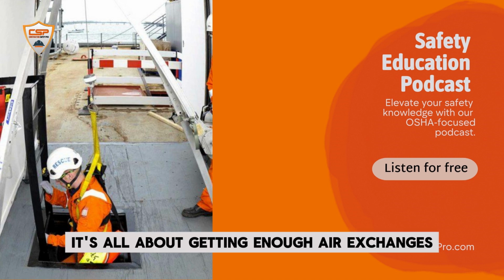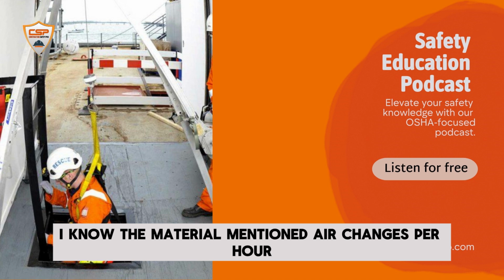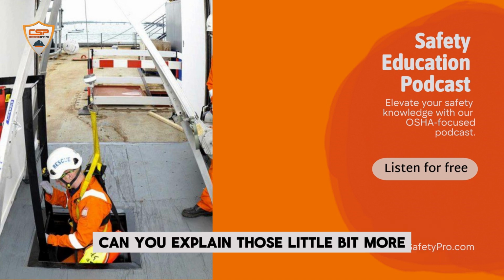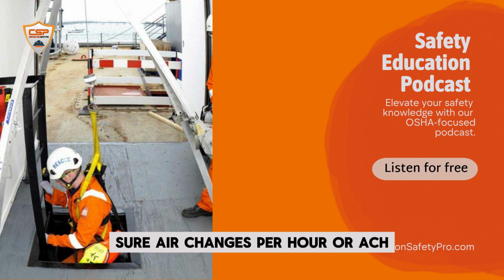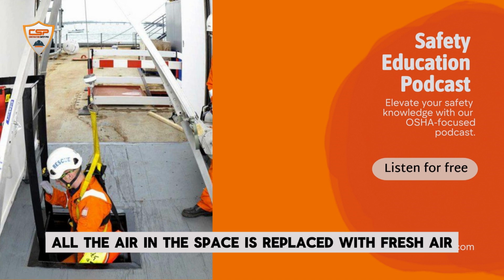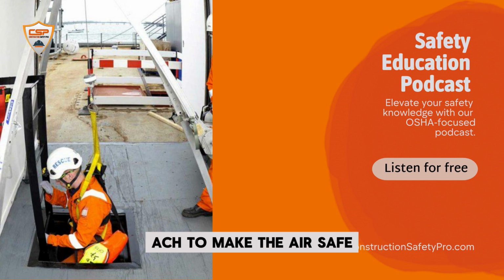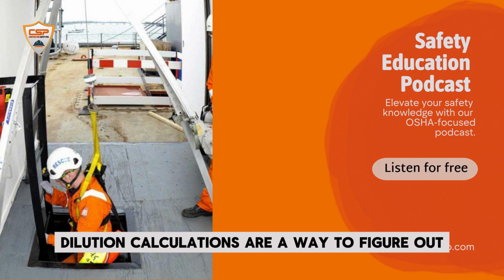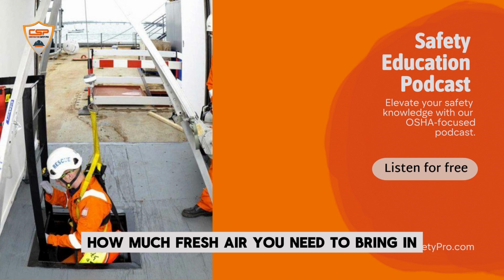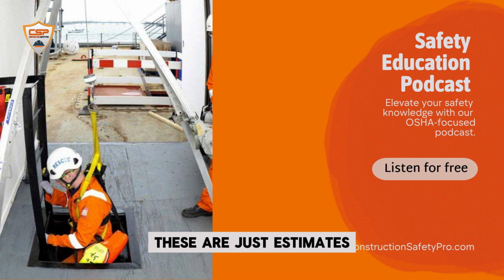Gotcha. So it's all about getting enough air exchanges to either dilute the contaminants or get them out completely. I know the material mentioned air changes per hour and dilution calculations. Can you explain those a little bit more? Sure. Air changes per hour, or ACH, tells you how many times all the air in the space is replaced with fresh air in 1 hour. Depending on the hazard and how risky it is, you might need a certain number of ACH to make the air safe. Dilution calculations are a way to figure out how much fresh air you need to bring in to lower the concentration of contaminant to a safe level. But remember, these are just estimates.